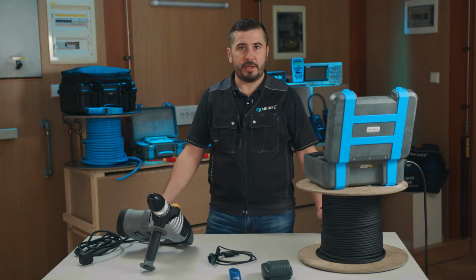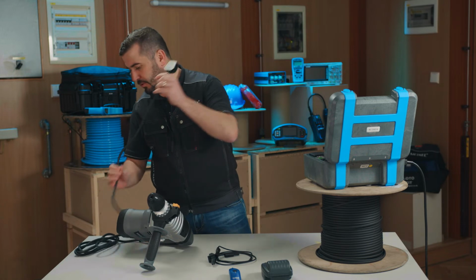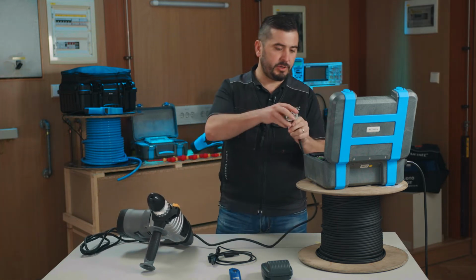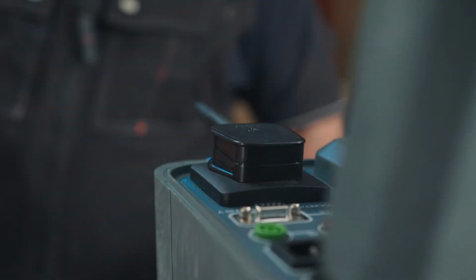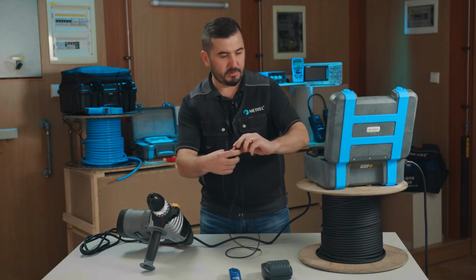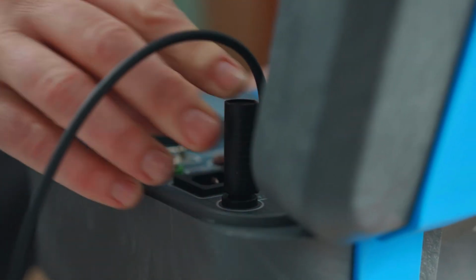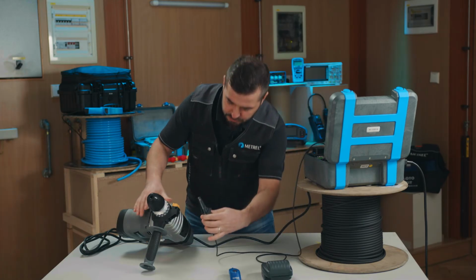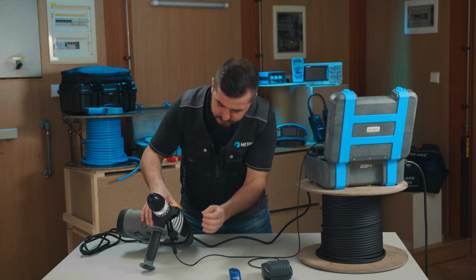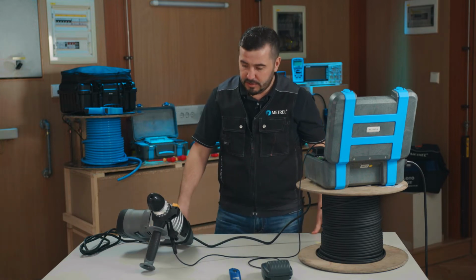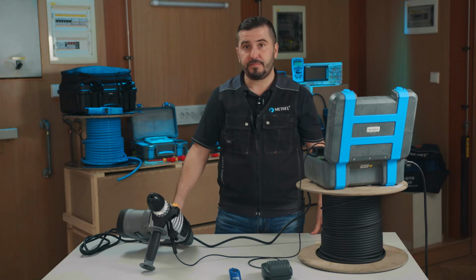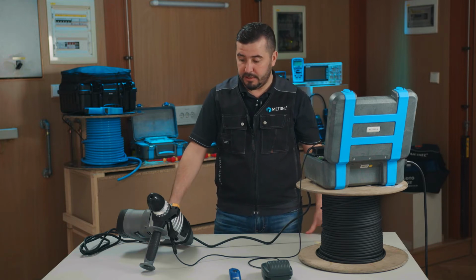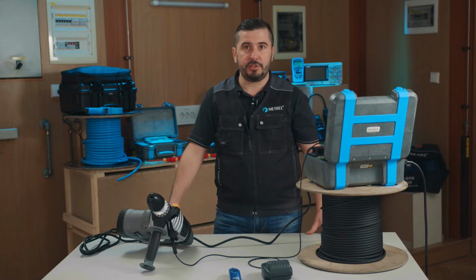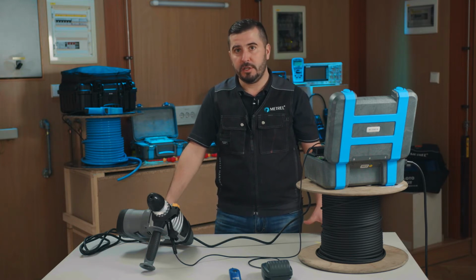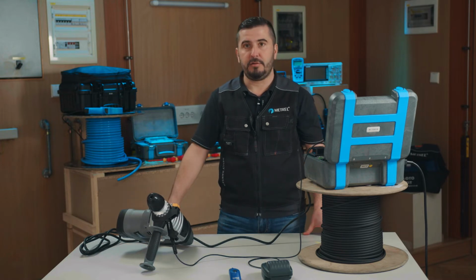So, now we connect everything accordingly. First, we will connect the mains plug of our rotary hammer to the mains test socket of our test instrument. And we will attach this test lead equipped with a crocodile clip to the metal part of the housing. This test lead will serve for detecting any integrity loss of the insulation, and of course if there is any flow of leakage current against this metal part.